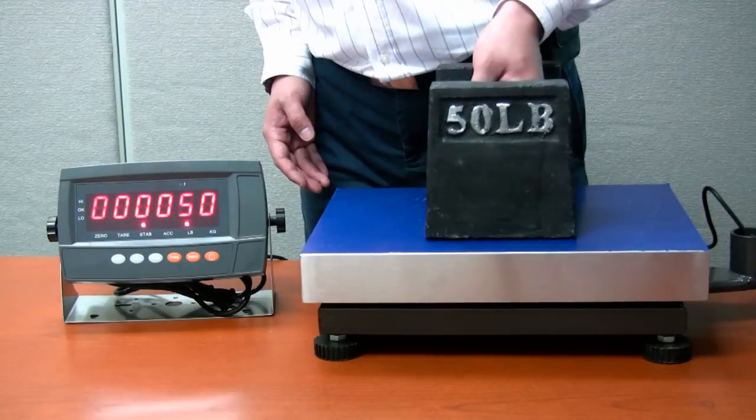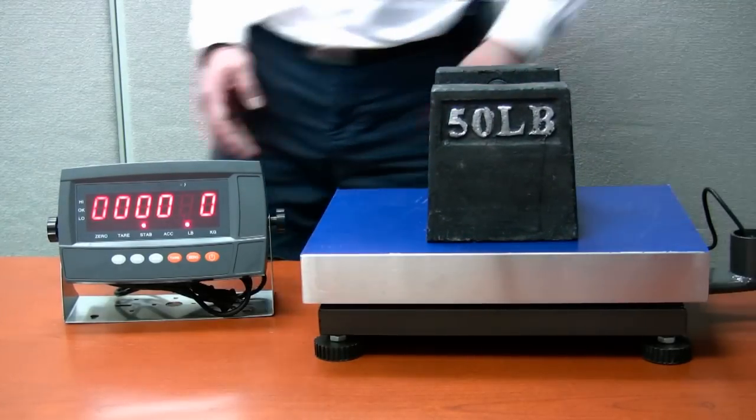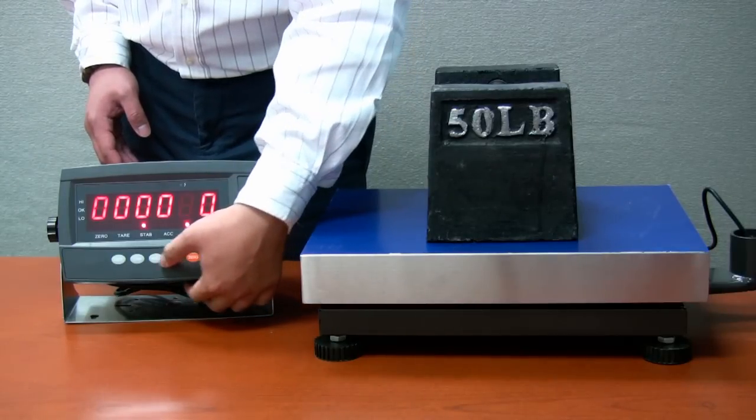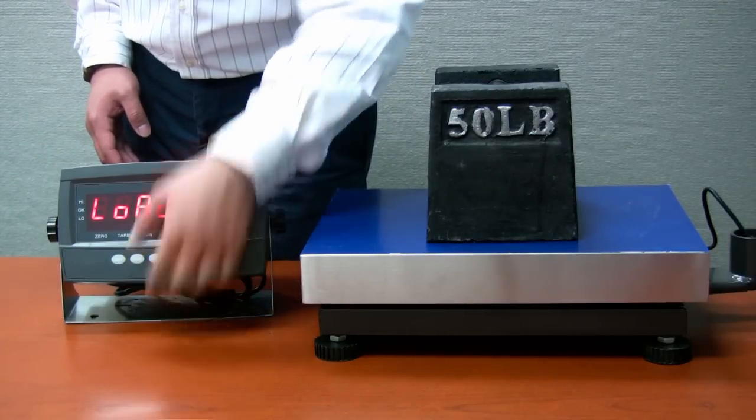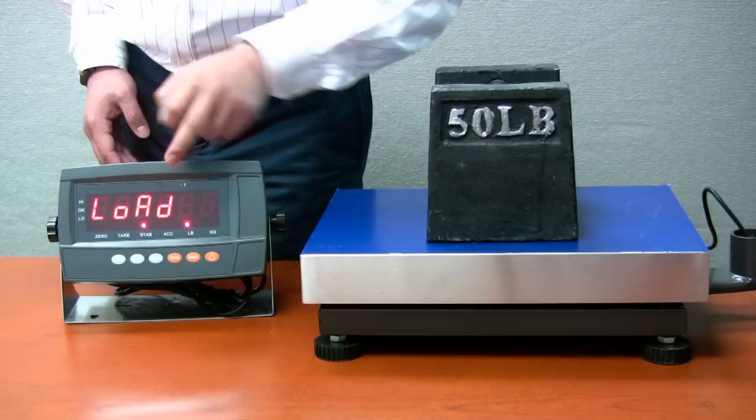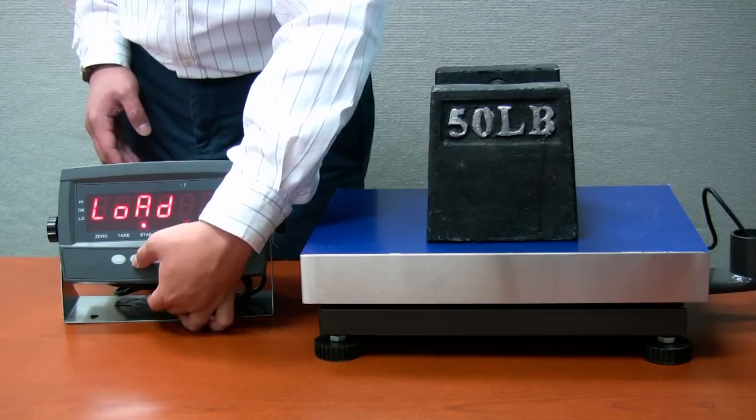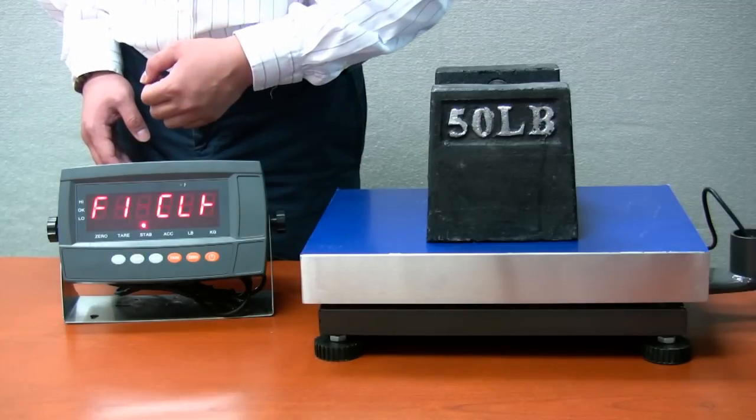Place the calibration weight on the scale platform. Press function key and the indicator will show load. Check the indicator's stable light, make sure it is on, press function key. The calibration is completed.